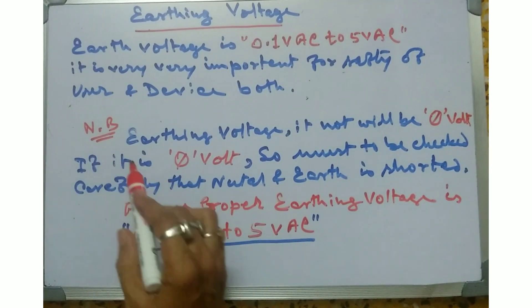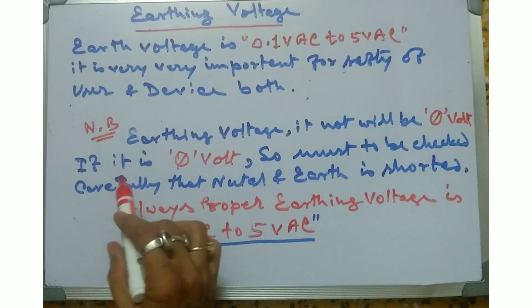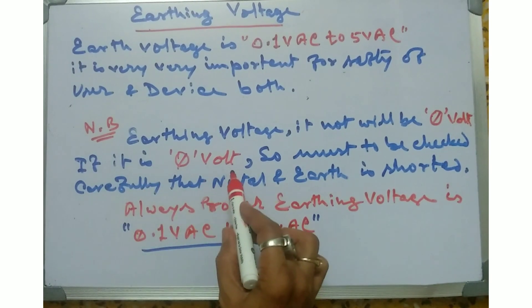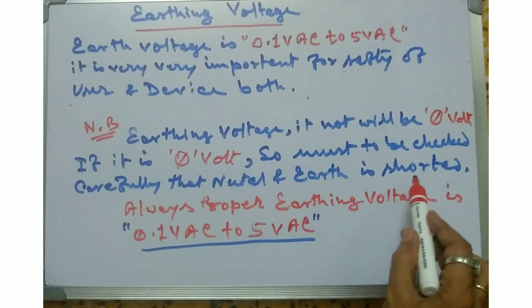Important note: NB earthing voltage should not be zero volts. If it reads zero volts, you must carefully check that the neutral and earth are not shorted.